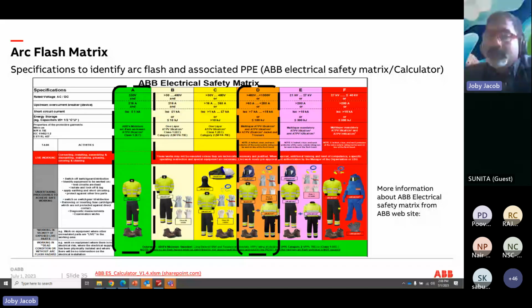So column C protects your full body. You protect your body plus your face plus your hands and plus your feet actually. And as the voltage increases up to 40 kV, and you go up to 40 kA, you go up to category F, and you get protected to the maximum. That's 40 cal per centimeter square. If the incident energy is more than 40 cals, it is very impractical to protect you by wearing PPE. So rather, we adopt engineering controls like remote switching and all those things actually.